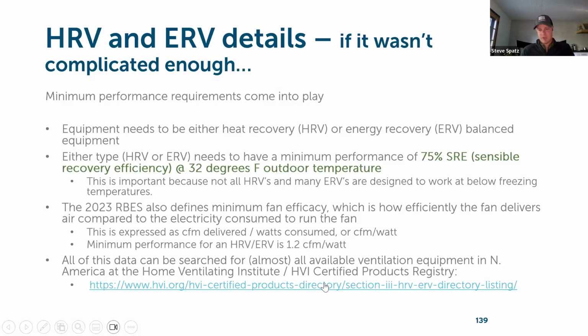So the minimum performance requirement again here, this should be 70. That's a change that was recently discovered in the code content. So 70% SRE at 32-degree outdoor temperature, to the question that was raised a moment ago. It is something to be very much considered when looking at equipment, as to its capacity and ability to still work when it's below 32 degrees outdoor temperature.